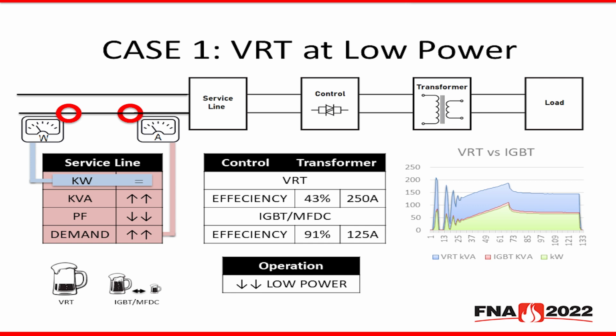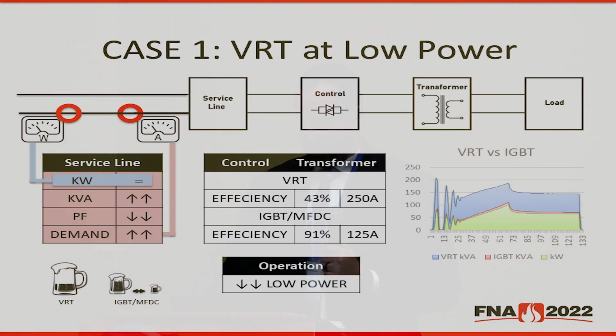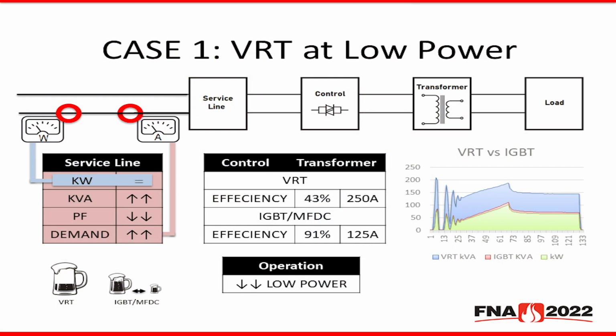And these inefficiencies really impact the bottom line. If we go back to the standard model that we described earlier, more kVA demand is billed, either directly through kVA billing or indirectly through power factor charges or peak demand charges. How much? An impressive way to describe this case is with peak demand. With a VRT system in place, the peak demand was 250 amps. However, with that kVA inefficiency addressed, the peak demand was reduced to 125 amps, or 50% less.